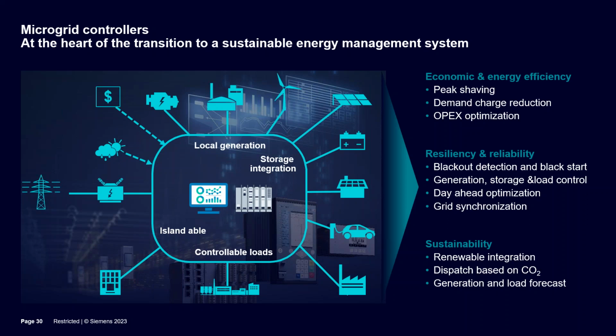There's also sustainability benefits, in that the microgrid controller will allow your on-site solar generation to continue producing electricity even when the grid is down. Otherwise, that solar would shut down because it doesn't have a signal to follow. So it allows for extended use of on-site renewables. It can make dispatch decisions based on carbon dioxide levels and sustainability objectives, and it can do forecasting for optimization of battery dispatch, among other things. So a number of benefits the microgrid controller can provide.